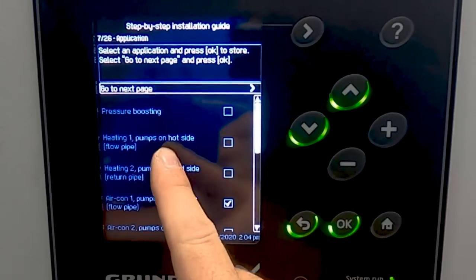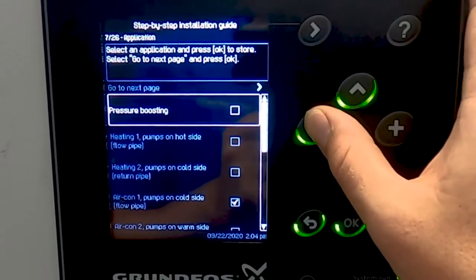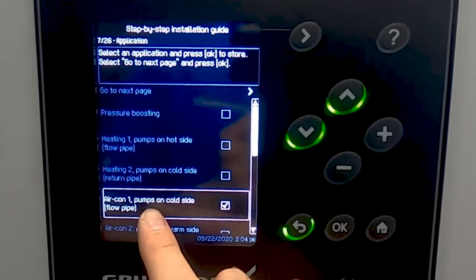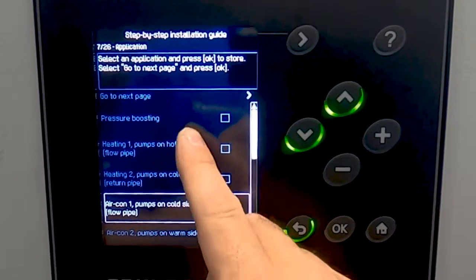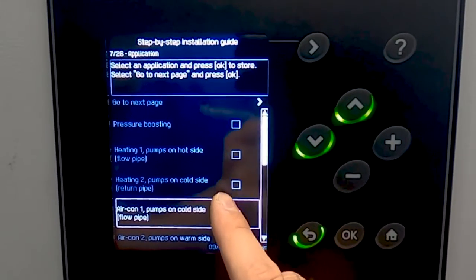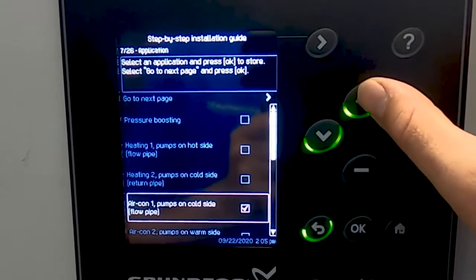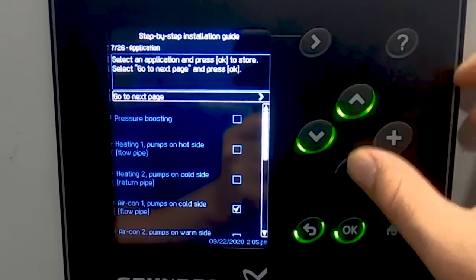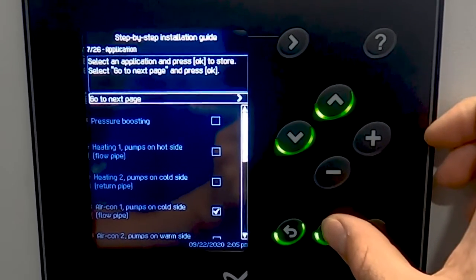The next step is picking the application in which the system will be operating in. For our system, we're going to pick air conditioning pumps on the cold side — this would be flowing away from a chiller. Note you could pick pumps on the hot side or cold side for heating and cooling, so this would be to or from a chiller or to or from a boiler. Once you have the application selected, you can go to the next page.